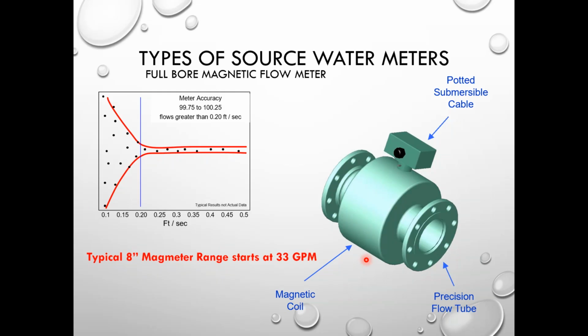And I have seen these in wastewater facilities that are operating under the minimum requirements of 33 gallons a minute. And so you definitely want to look at the minimum ranges of mag meters. Here it shows the meter accuracy is really good until you get to about 0.2 feet per second. At 0.2 feet per second, the accuracy just falls way off.